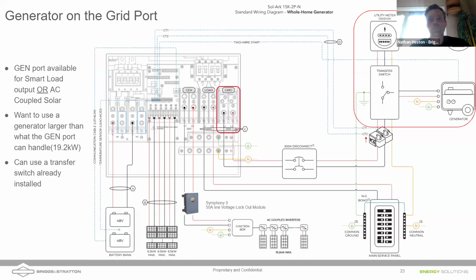Yeah, and like you mentioned, Nathan, it could be a manual. So in this example, you'd still have this transfer switch, and then you'd be connecting these here, so you would be able to bypass it as well, with a secondary one after those CTs, bypassing the inverter and going straight to that main service panel that's there. So thank you. Yeah, and if you brought the generator into the gen port, you would only need one transfer switch.